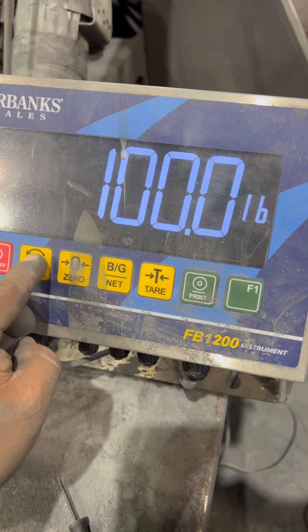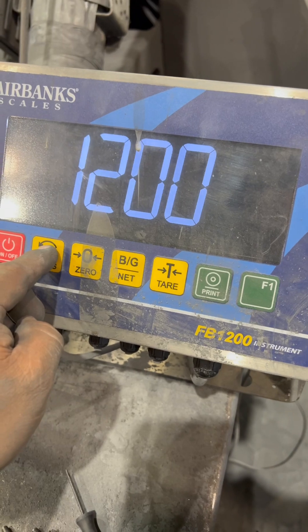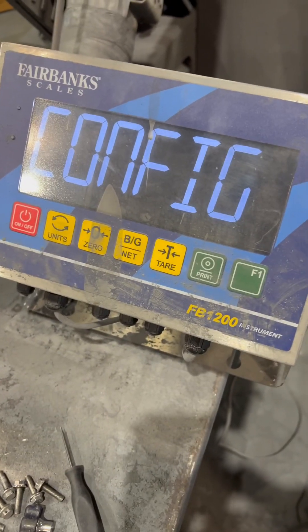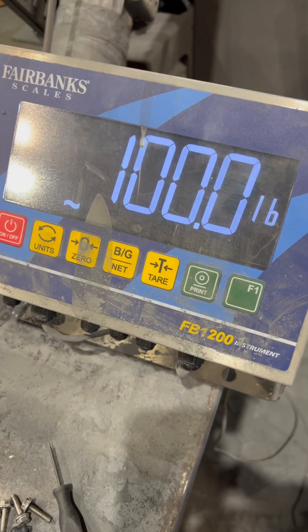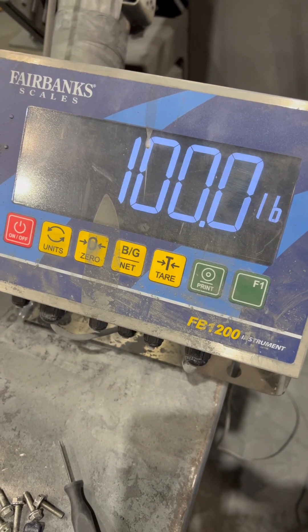You've now set the span. Use the UNITS key and keep pressing it until you see 1200. At this point, let it go and it will bounce out to weight mode on its own. And that is how you adjust the calibration of the Fairbanks FB1200.